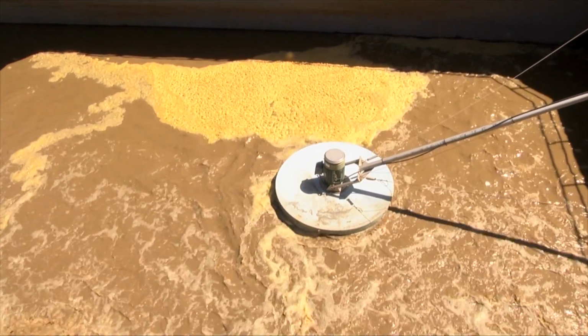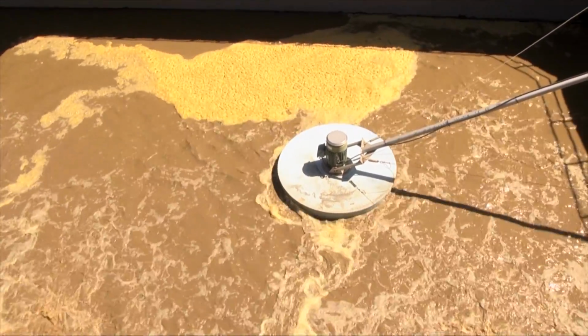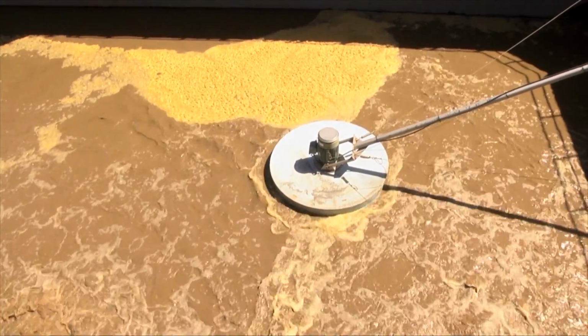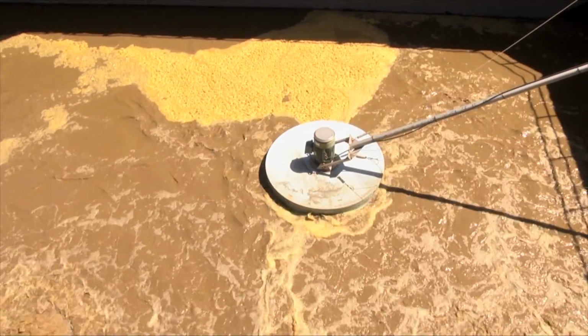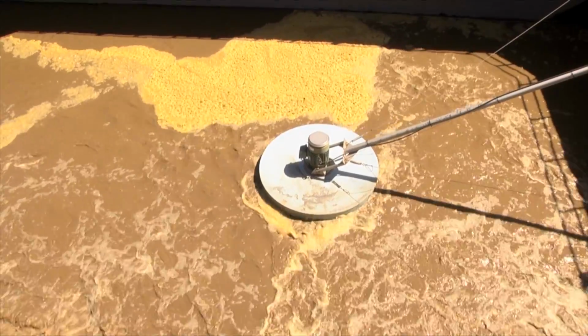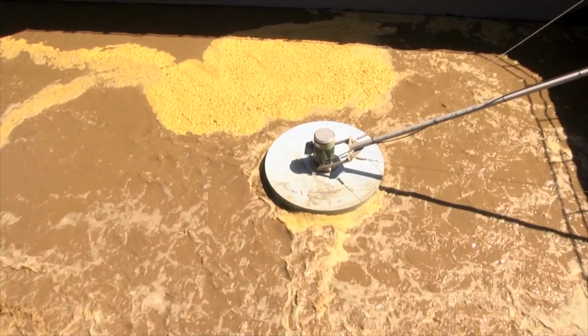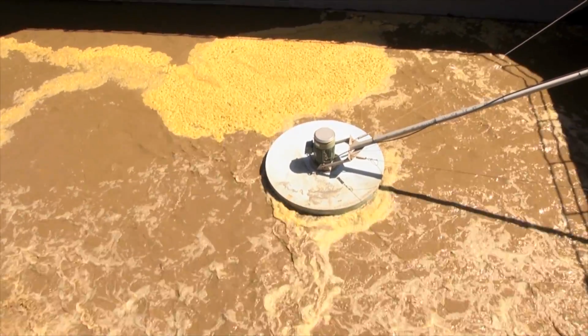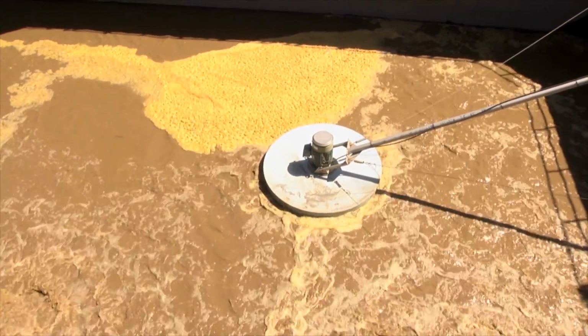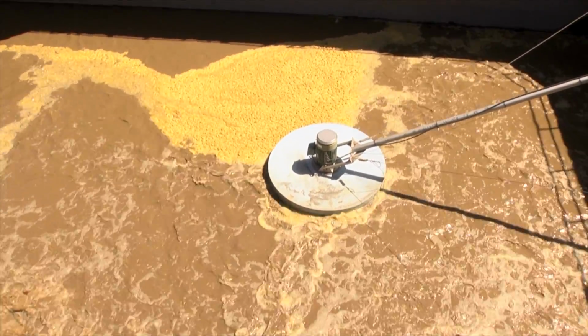So this right here is our digester. As you can see, we have mixers in there just like over in the SBR itself, and we also have air going into the wastewater there. Now, as your biomass is breaking down waste, it's actually recreating new biomass. So through a series of tests that we do, we have to judge the exact amount of biomass we need to give us our best treatment. So we actually have to cast off some of that, which is called wasting. So this is extra sludge that we generated that we'll put into this basin.